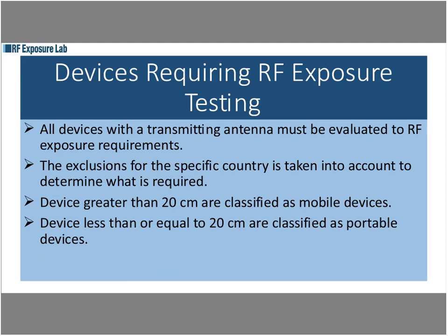So, devices that require RF exposure testing. Well, all devices with a transmitting antenna must be evaluated to RF exposure requirements. A lot of people say, well, my device is greater than 20 centimeters, I don't have to do anything. Now, it still has to be evaluated. It's just you're now evaluating to a mobile device rather than a portable device. But if you've got a transmitter in a device, it has to be evaluated for RF exposure requirements.